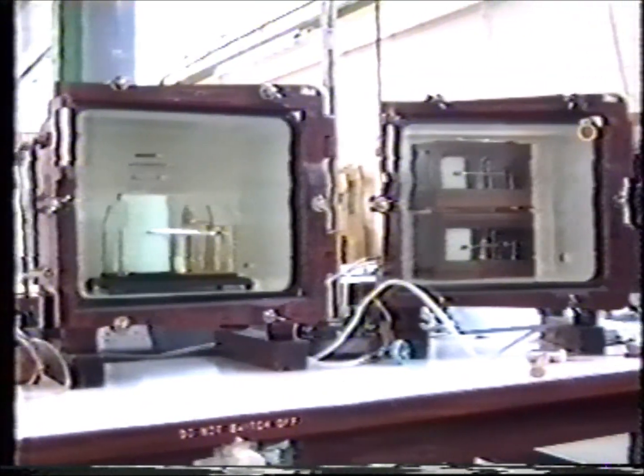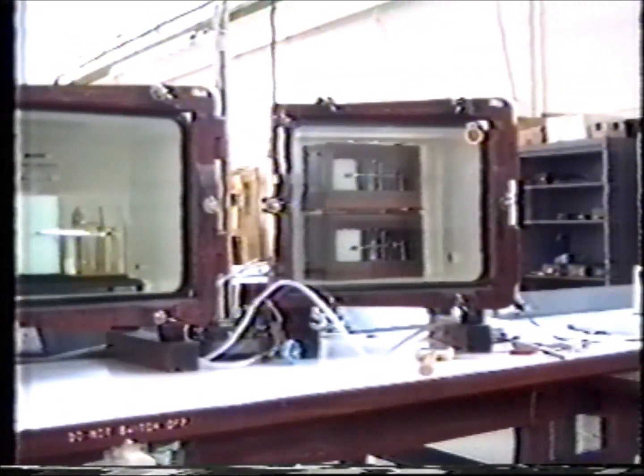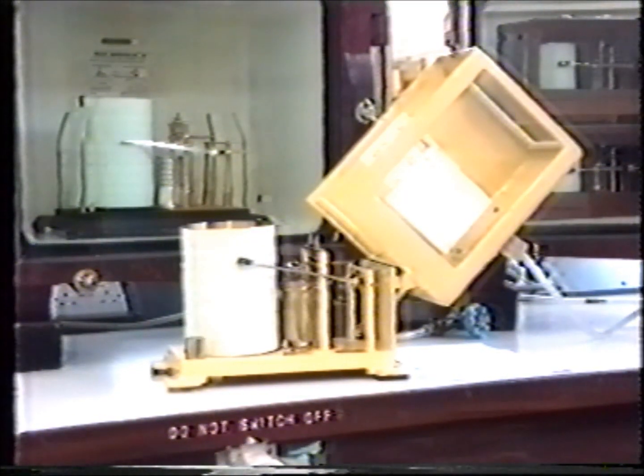Several types of barographs are calibrated. The Met Office open scale type on the left and the Navy display barograph shown here on the right. The marine barograph is unusual in having an oil-damped mechanism to provide a clean pressure trace even in very rough conditions at sea. These, like the aneroid barometers, often arrive from the ship as a kit of parts.